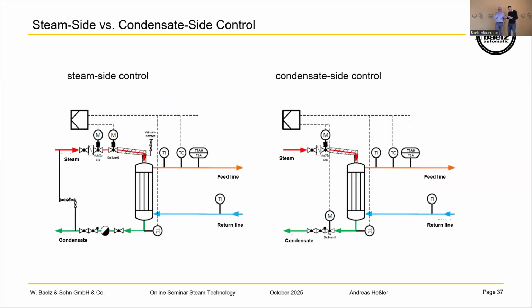The question is, is it best practice to install a steam trap in series with the control valve? No, it's not possible. When you mount a steam trap, as you see on the left side, you make a steam side control. Because when you use a steam trap, you always have no condensate inside the heat exchanger. So you're not controlling anything. It means you always have 100% power of the heat exchanger, and it simply is not necessary. When you have a control valve on your condensate side control, there will always be only condensate.